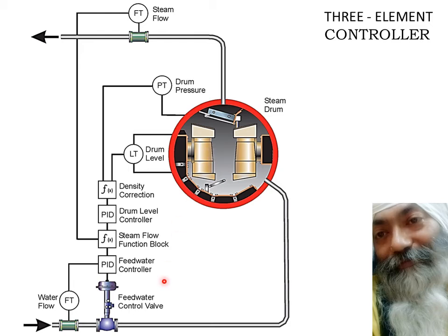So in normal conventional control, if the level increases, the inlet of feed water reduces, but this has understood that it's on account of swelling, and the inflow should not reduce, rather the inflow should increase in anticipation of the level going down because of increased steam flow.